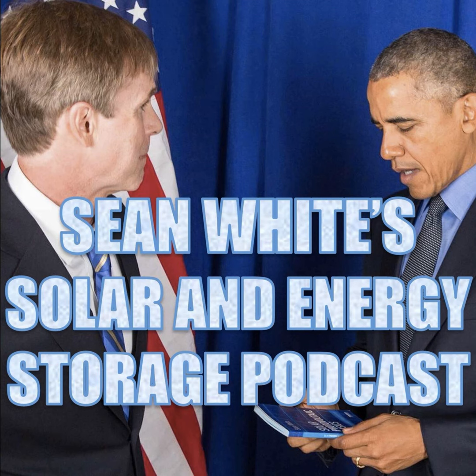So then when we're doing this with adding solar or energy storage, today's energy storage day, but it's the same thing for solar, instead of just taking that 150 amps, what we could do is we go 150 amps plus 125% of inverter current. So there's a 32 amp inverter, that's an energy storage inverter today, times 1.25 is 40 amps, that's 125% of inverter current. And so then we end up with 190. So 150 plus 40 is 190. And then we are going to multiply that times a third, or divide by 3. And then we're going to get 63 amps. Make sure that conductor's at least 63 amps.